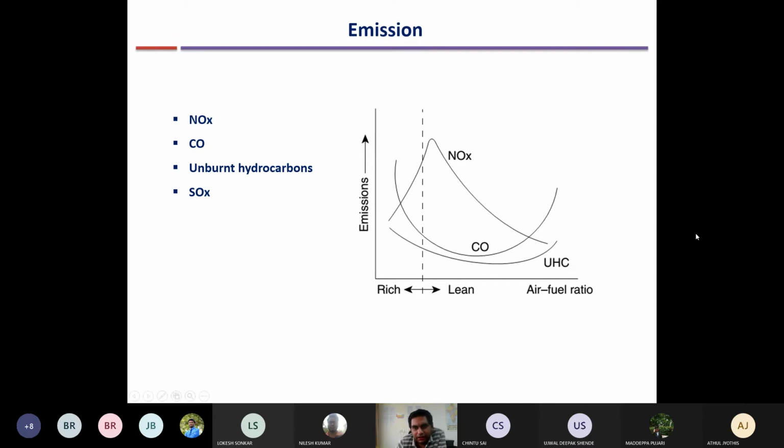But when there is optimum air fuel ratio, then there may be quite high NOx formation. Okay. But in our case, this is the stoichiometric ratio, so maybe somewhere around there. So slightly less than that, NOx formation is there. And for industrial gas turbines, once NOx is generated, you cannot stop it in the combustion chamber, but you have to use additional devices which are called selective catalytic reducers.